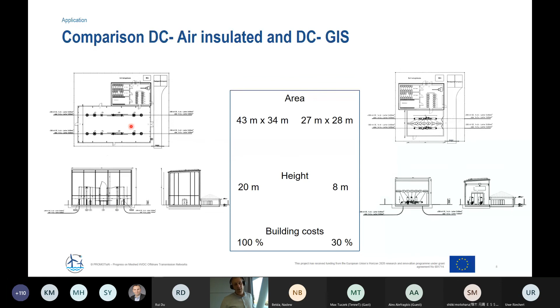Maybe we have already some existing installations at 420 kV. Maybe then for new installations we plan it with 350 or 550 kV. The rated current will be up to 4000 amps. Rated short circuit less than 40 kA, and maybe for the peak 56 kA. Lightning impulse, as you already see it in your previous presentations. We plan all our installations indoor, and so the ambient temperature should be between -5 degrees and +40 degrees.